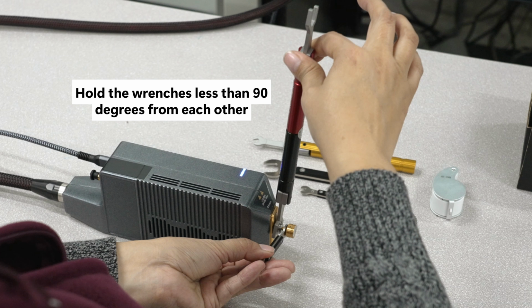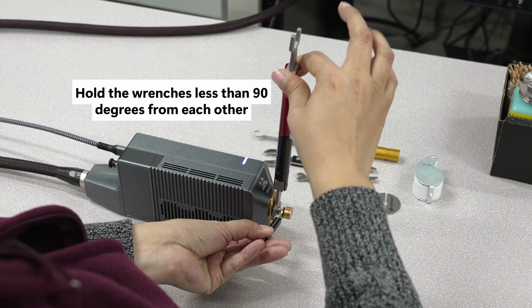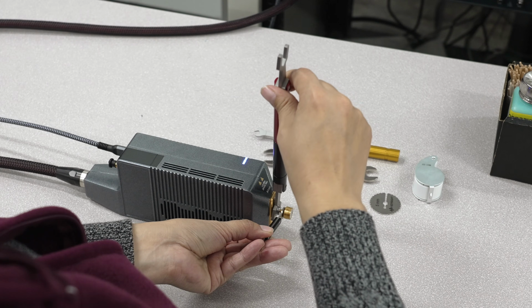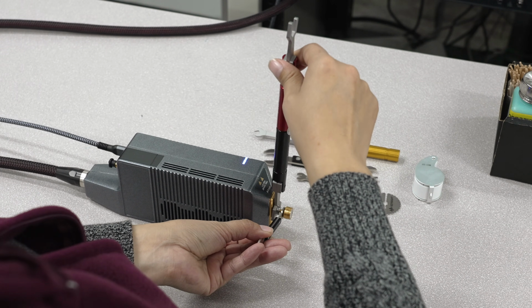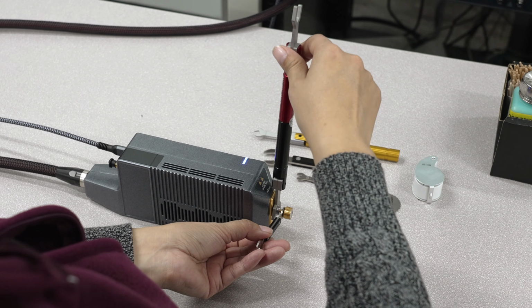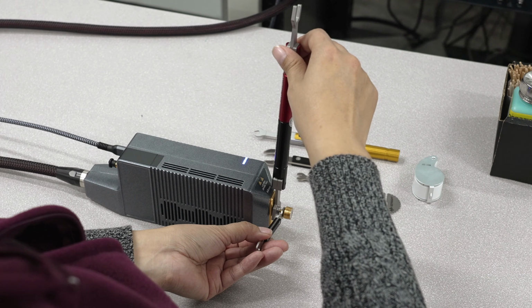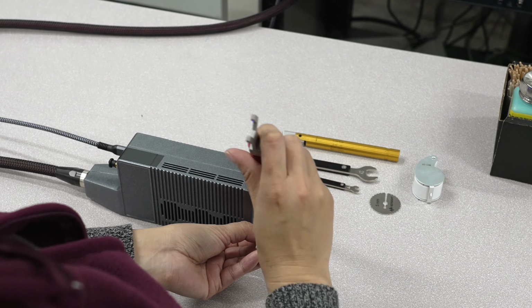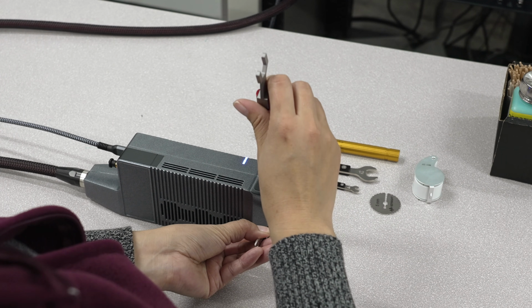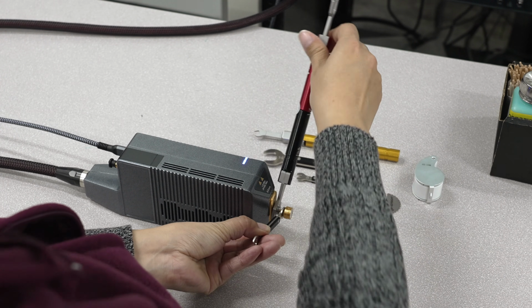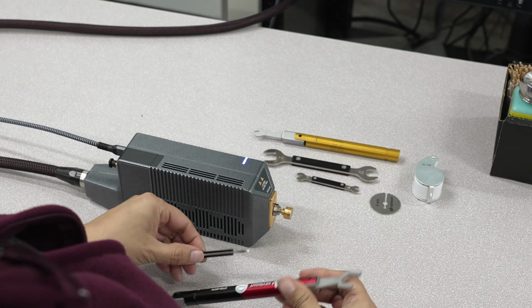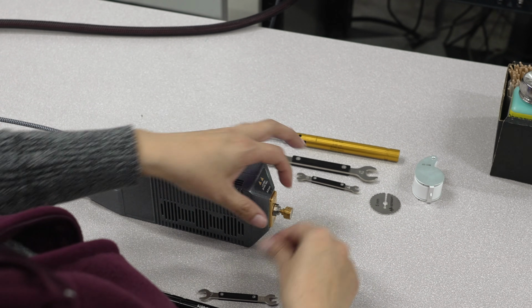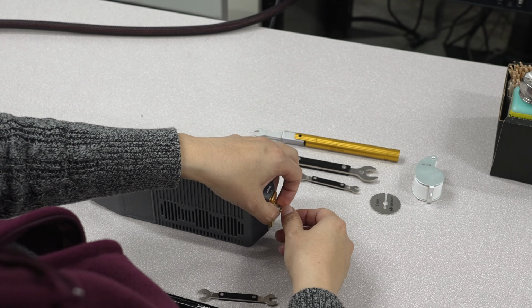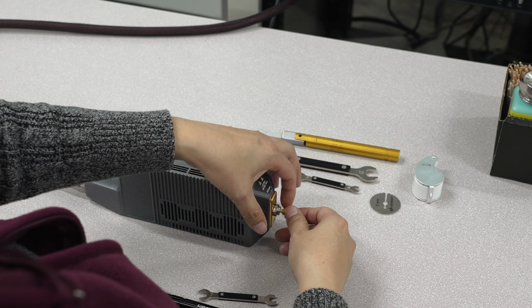Ensure that the angle between the torque wrench and the back-off wrench is less than 90 degrees. Only apply enough torque to just break the wrench as shown. For more information, the double-ended torque wrench user manual is linked at the end of this video. To disconnect the device, preload the back-off wrench and turn the nut using the torque wrench in the opposite direction. Then finish unthreading by hand. Gently disconnect the device by pulling straight back to avoid damaging the center conductor.